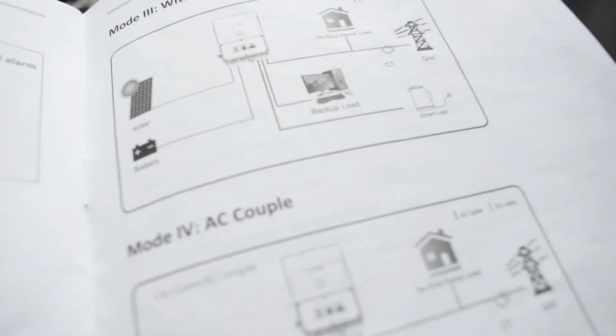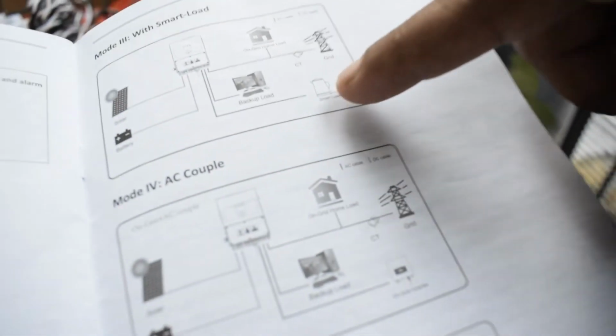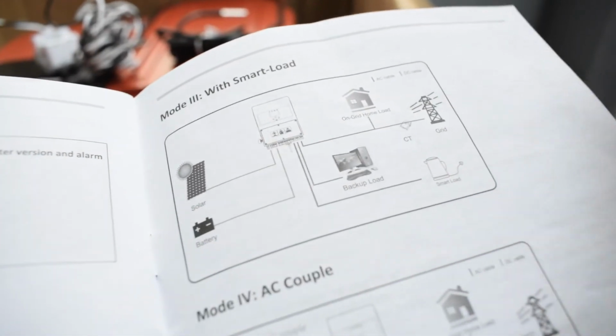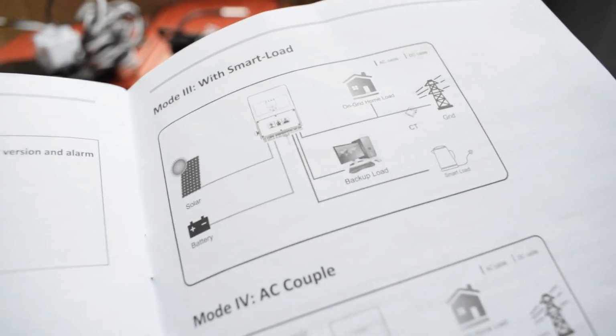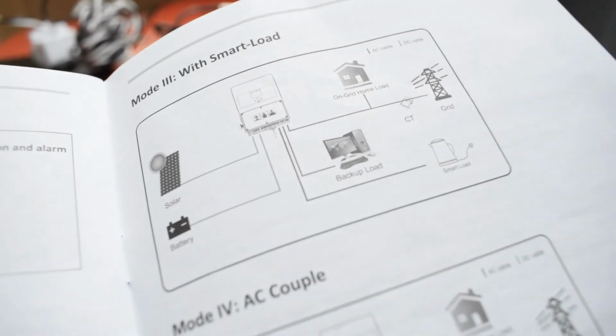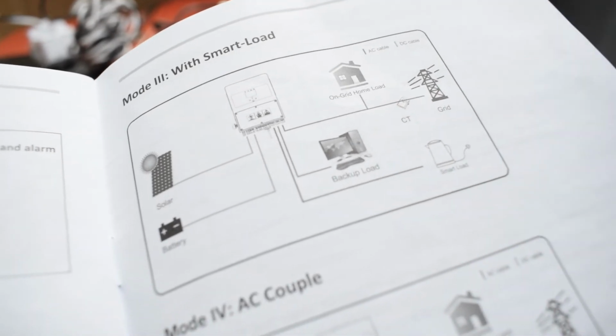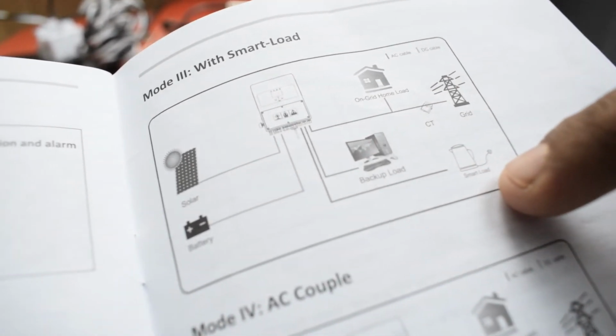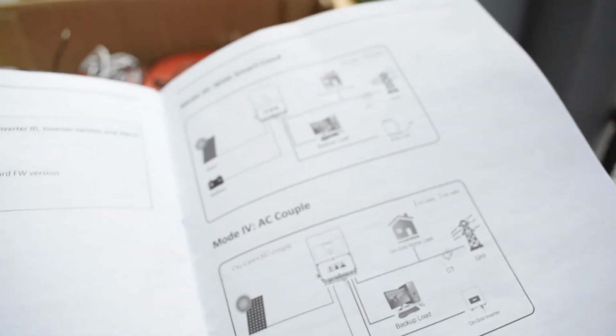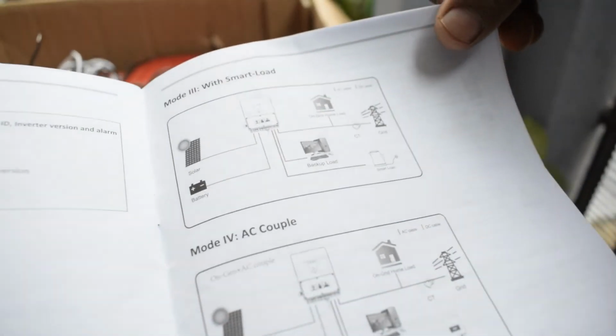The third mode is the smart load. We utilize the generator port with the smart load. Okay, this generator line and neutral will connect with the load which has very high power consumption, like a resistive electric kettle or air conditioners or any high ampere motors which cannot be utilized continuously. So we connect this load with that smart load, and the main load is connected with the backup load for PCs and for the fans and lights, and the last load is also always on the grid.